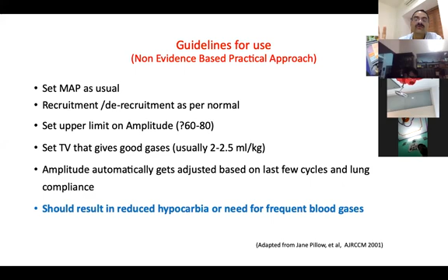Once you set your tidal volume to 2.5, amplitude max, you have kept a value. The first thing that you look at is, with this amplitude, am I reaching my tidal volume? If you are not reaching, then probably you cannot go more than 60 and all that amplitude, isn't it? So you would need to adjust your frequency to get your tidal volume right. Always aim for a higher frequency with spare amplitude available.